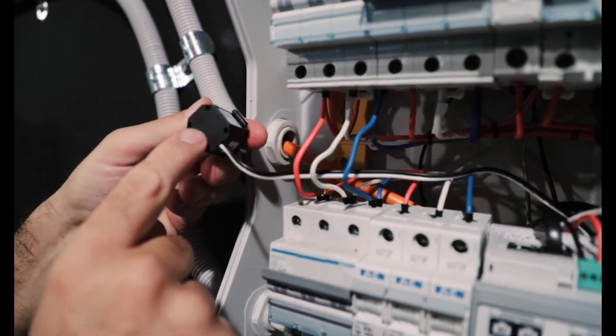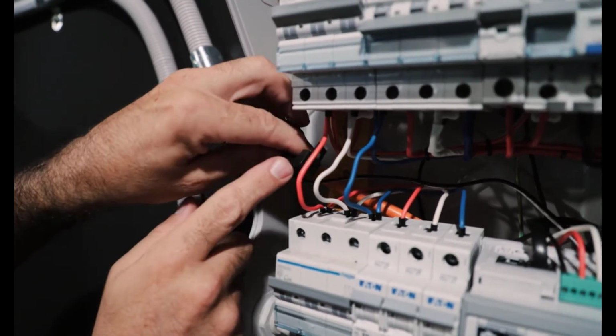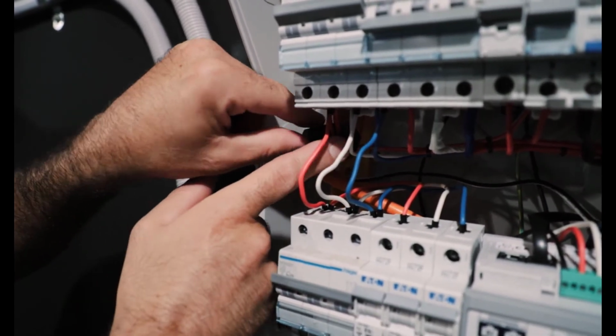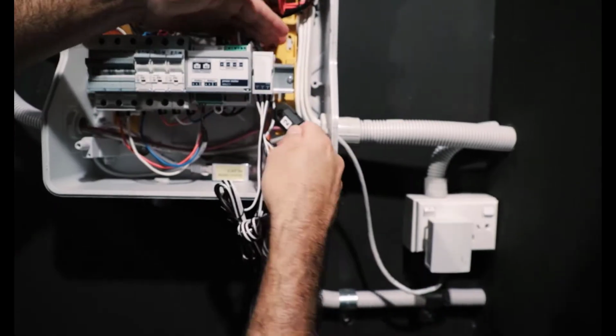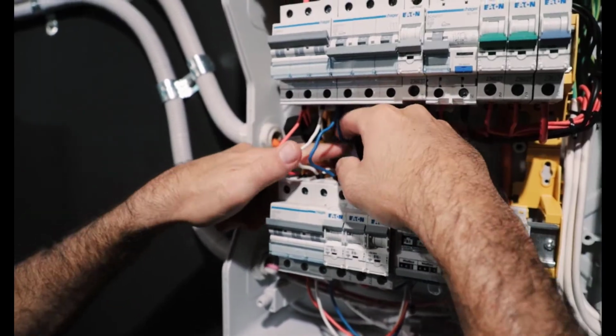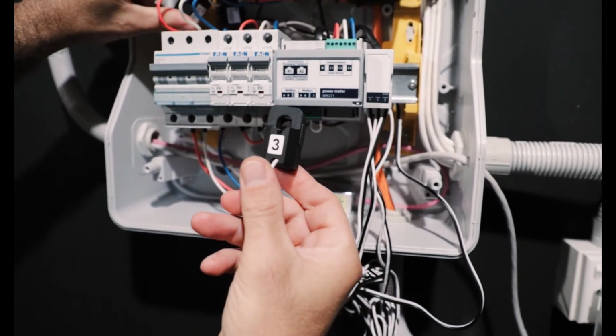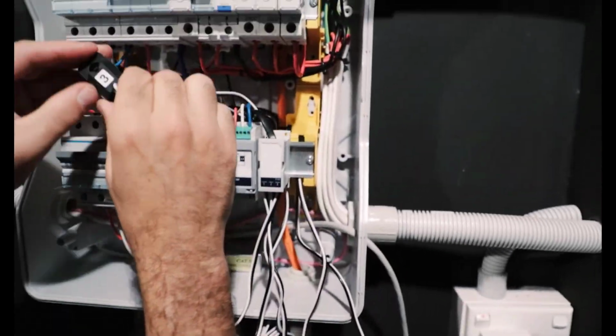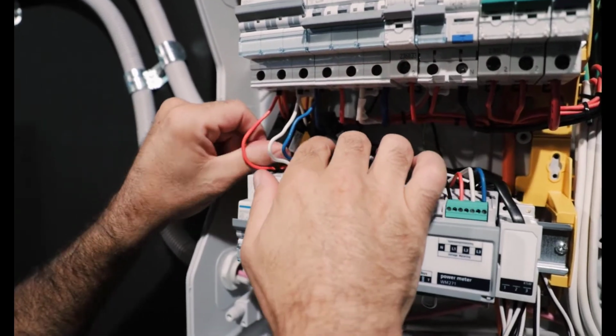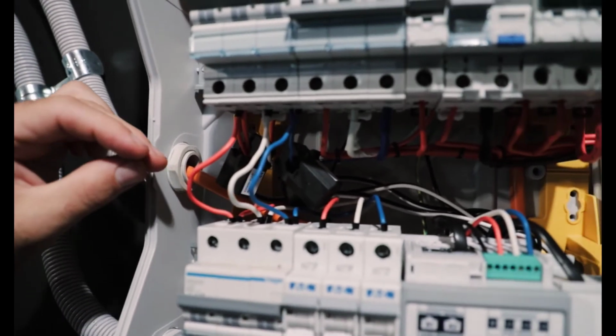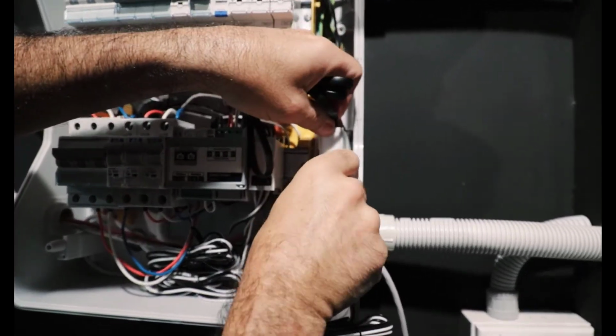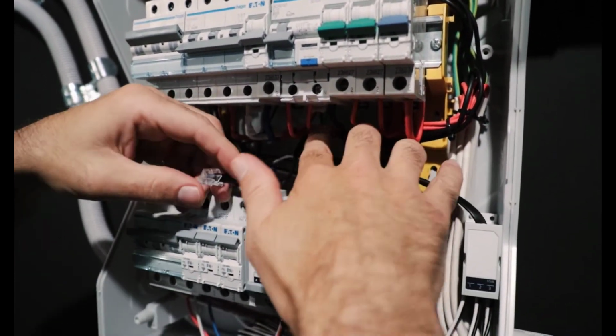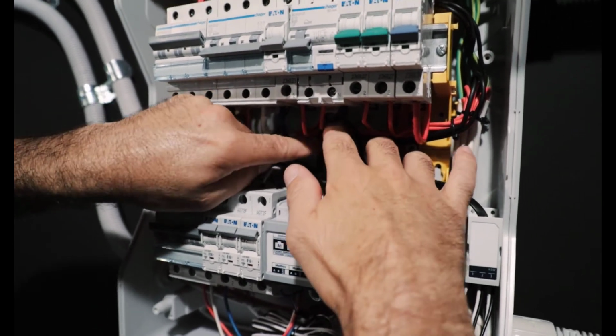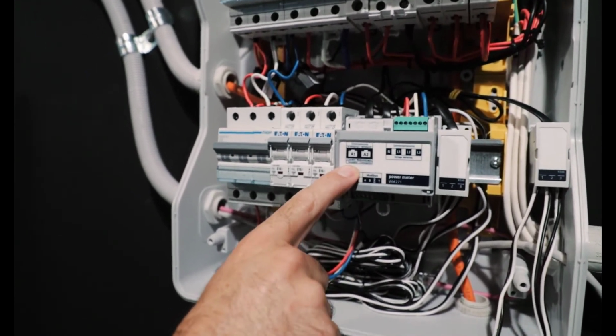So now, as this is consumption measurement, we're having to separate out the AC just going to the load circuits. So as you can see, I'm not CTing the loads for the sonnen system, they are separate. It's purely the load coming out of the main isolator going to the load circuits. So not included within that is the power flow from the sonnen system or the PV. And lastly, CT number 3. So using this nice large switchboard, it's quite full in there, so I'd expect that most installers will be going for the grid measurement setup because that's simpler. Our CT set here going in for our generation, plugging that one into the A1 terminal. Again, as this installation's only got single phase PV, we're only going to be using CT number 1.